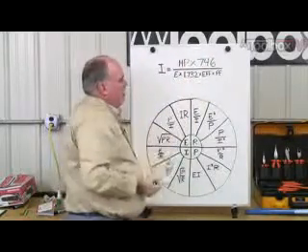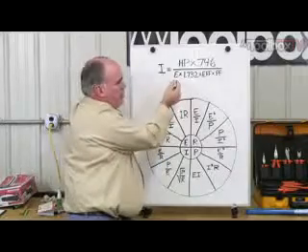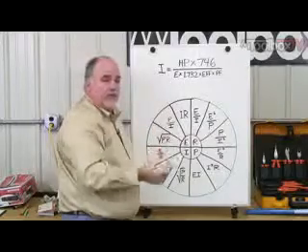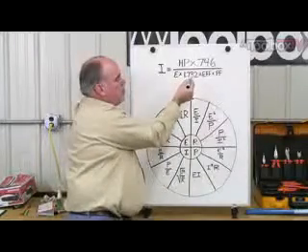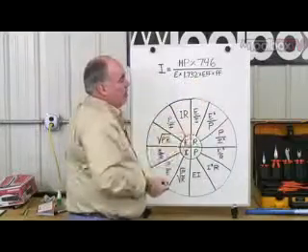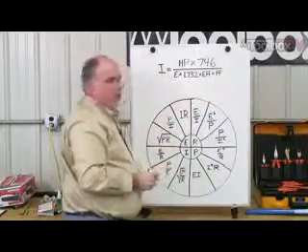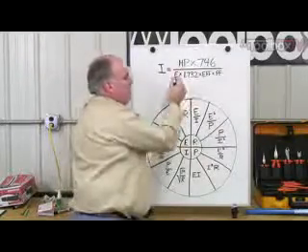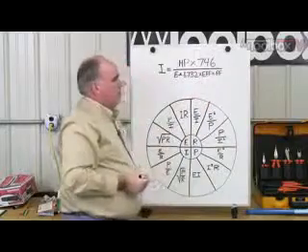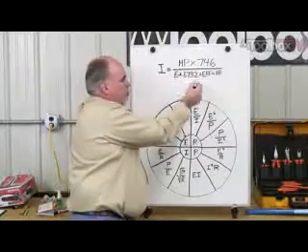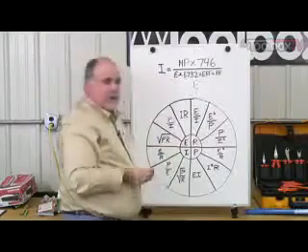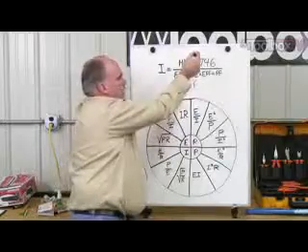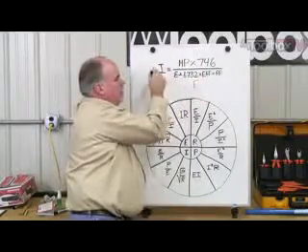The bottom side of the formula starts out with voltage, E, times the square root of 3, because it's a three-phase motor. So voltage times the square root of 3 times efficiency of the motor times the power factor of the circuit. We'll get into those things in another video at another time. But basically, the entire bottom side of this formula is to get us a true number of the voltage applied to this motor. Okay? Now, look at this. It's power divided by voltage gives you current.